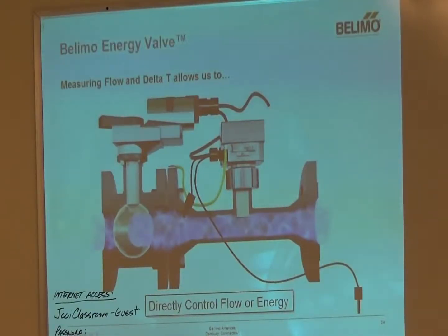It's used a lot for surgery suites, museums, libraries, places where it's critical control. So you'll see that a lot more there. It's a lot more applicable, because you're factoring in temperature too, not just flow, right? Yeah, when you're using that formula he showed earlier, Q is 500 times GPM times your delta T to get your actual power. But this is the standard energy valve. It's a standard feature of the energy valve.